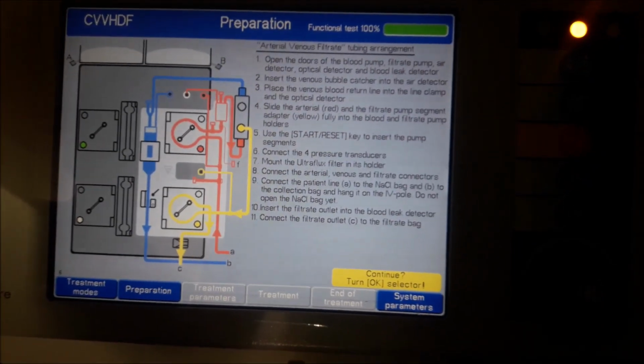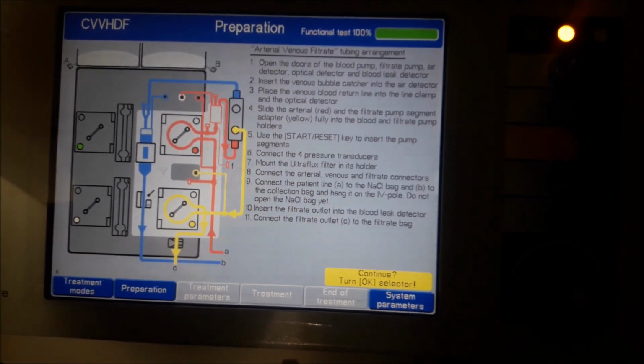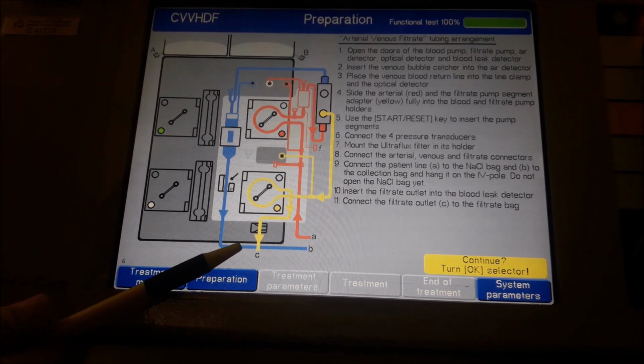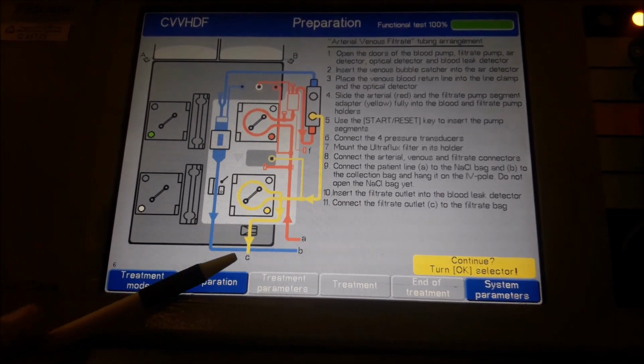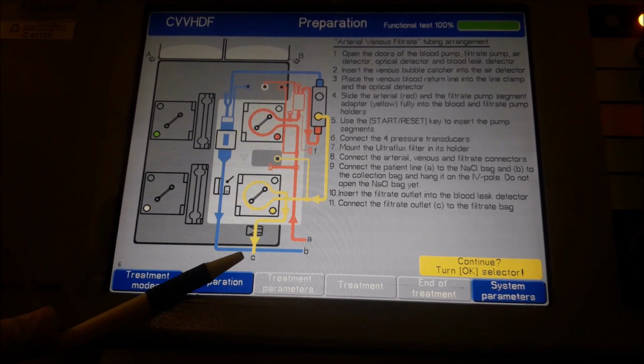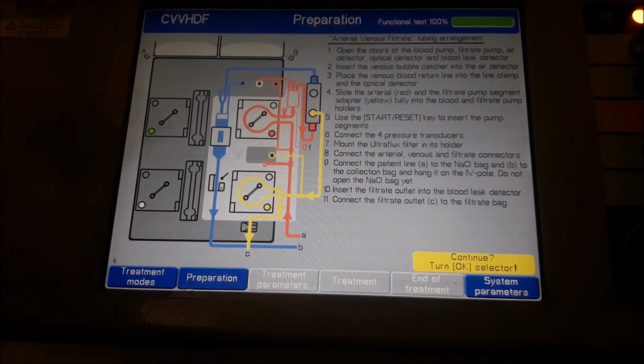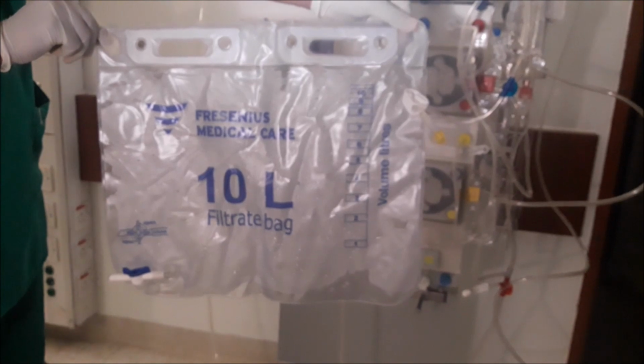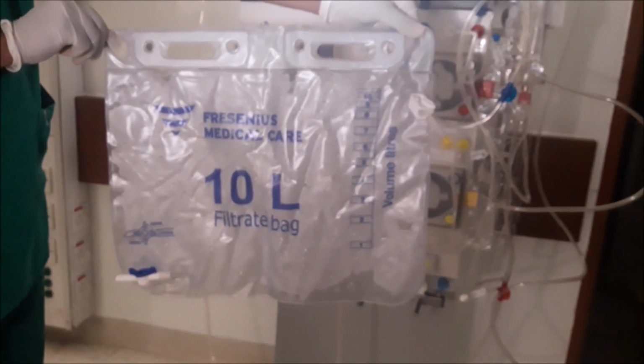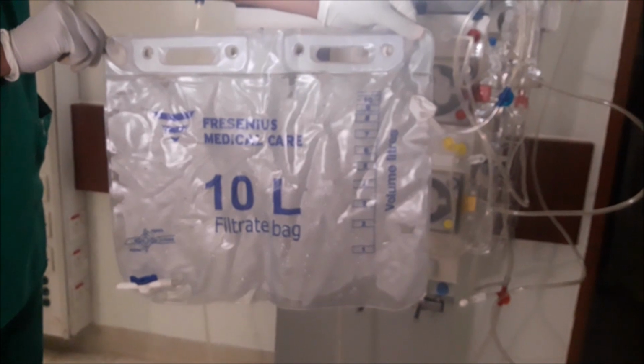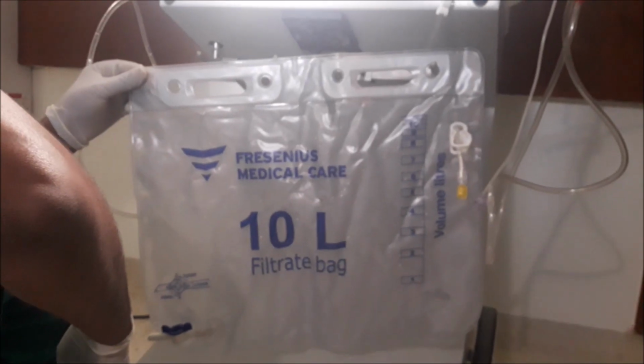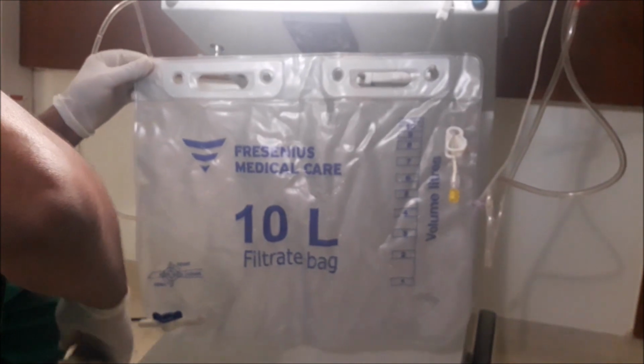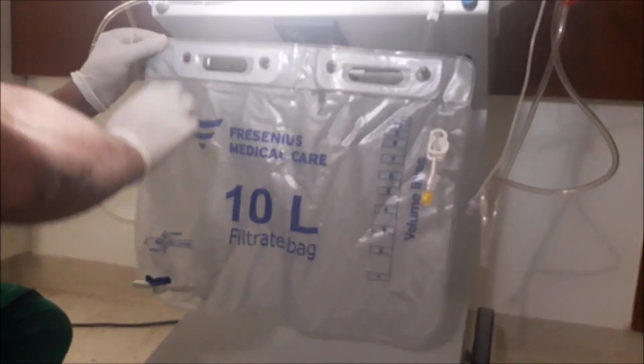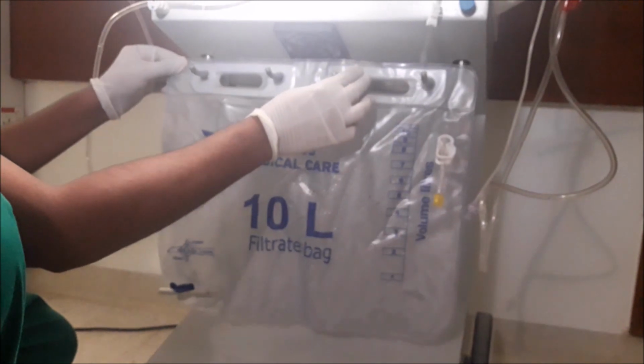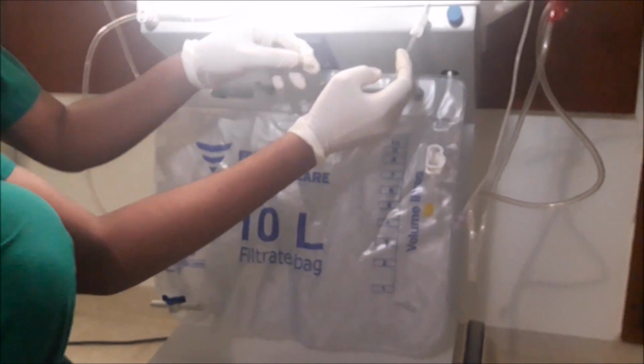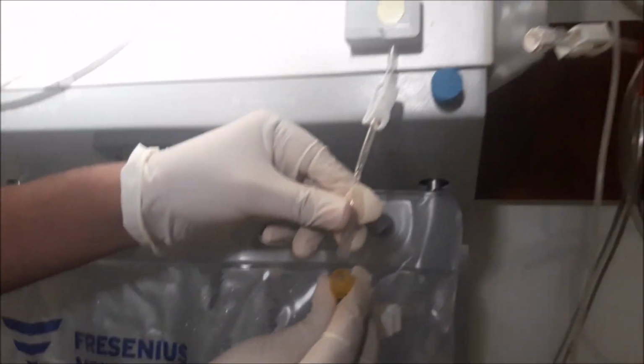Connect the filtrate outlet C to the filtrate bag. Let's see on a picture. As we can see in the picture, yellow is our C tubing. Now we will attach our filtrate bag to this tubing. This is called the filtrate bag, which is used for the collection of filtrate, and the maximum capacity of this bag is 10 liters. As mentioned in point C, firstly we will hang the ultrafiltrate bag on scale 3 and scale 4. After that we attach the ultrafiltrate outlet to the ultrafiltrate bag.